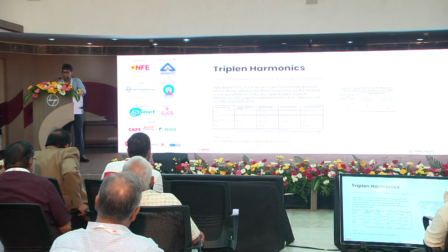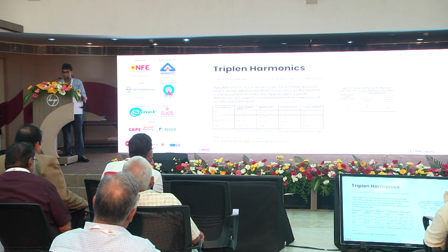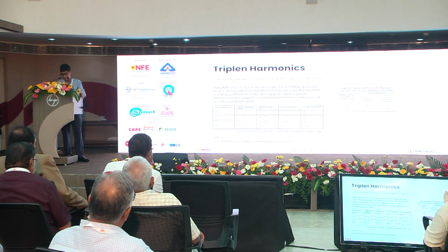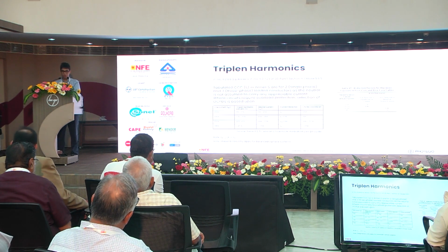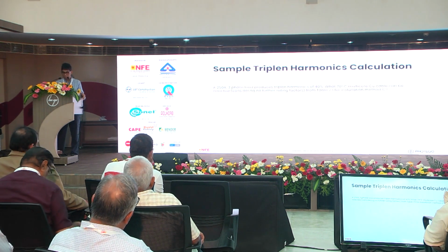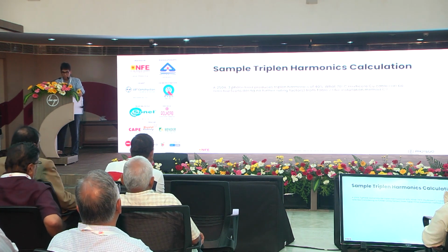And this is Table 45 from IS 732, and it is also there in Part 1, Section 9 of NEC, clause 5.6.5, which shows these exact factors. All I have done is got a table that shows it to you nicely from an IET design guide. Now let's perform a simple triplen harmonics calculation, basic third grade multiplication.